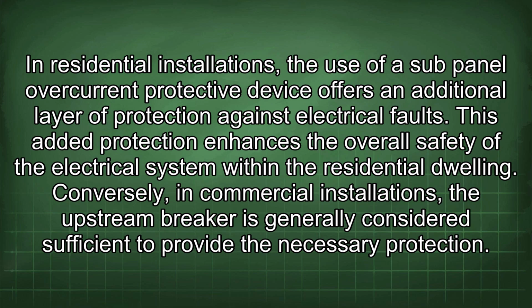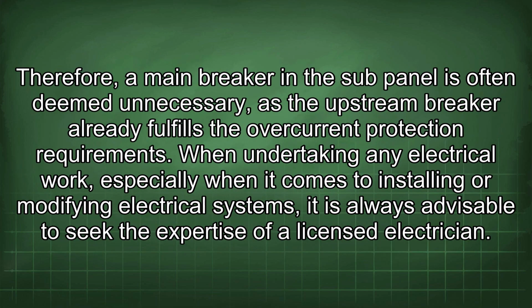Conversely, in commercial installations, the upstream breaker is generally considered sufficient to provide the necessary protection. Therefore, a main breaker in the sub-panel is often deemed unnecessary, as the upstream breaker already fulfills the overcurrent protection requirements. When undertaking any electrical work, especially when it comes to installing or modifying electrical systems, it is always advisable to seek the expertise of a licensed electrician.